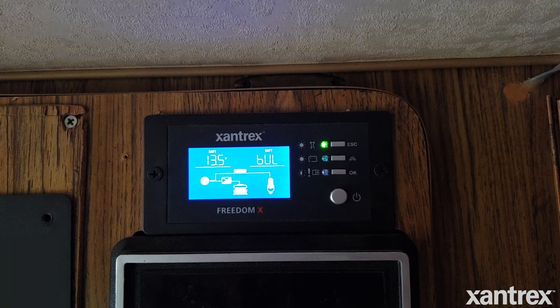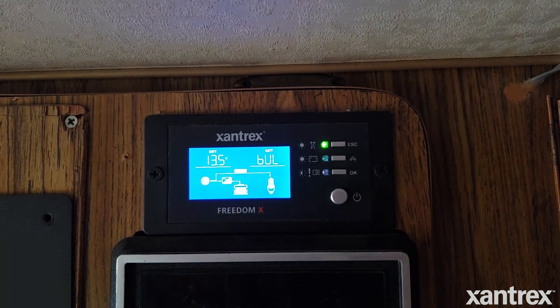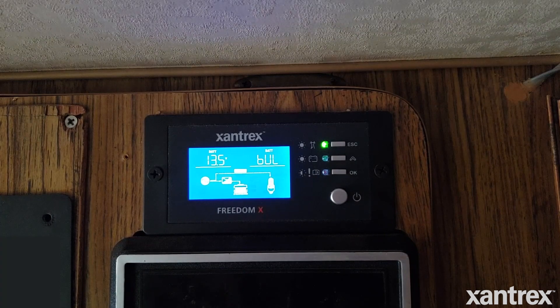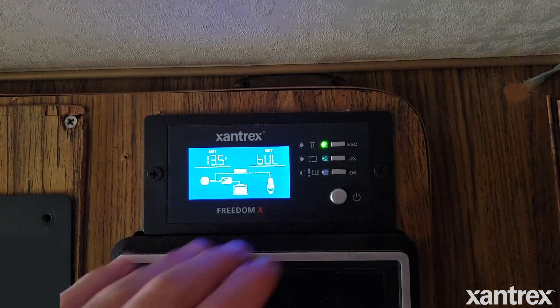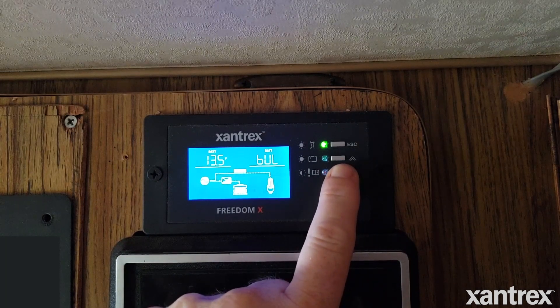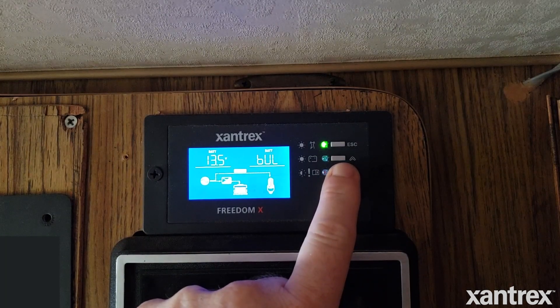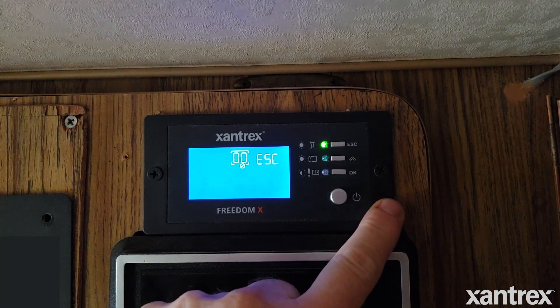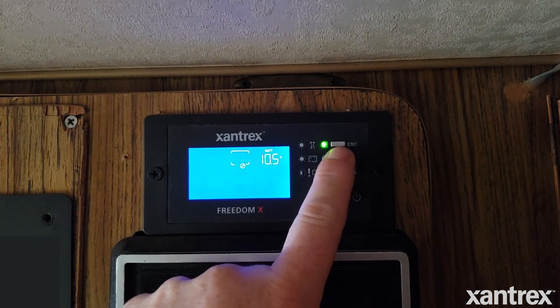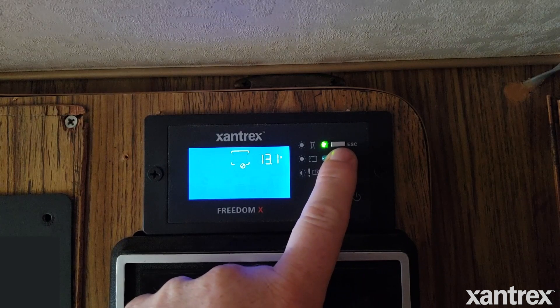Okay, so for the Xantrex Freedom X 2000 watt pure sine wave inverter control panel, to set it up for lithium, here's what we're going to do. We're going to start with changing the battery type. The way you interact with the settings menu is to push and hold the ESC button — there's going to be a beep. After you hold that down, you're in the settings menu. You can use the middle button to scroll through settings, and we're going to go right ahead to setting number 20.